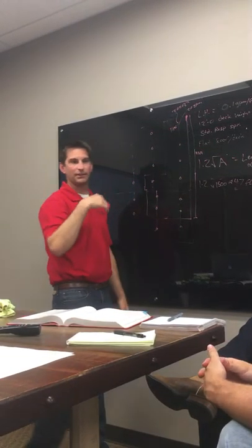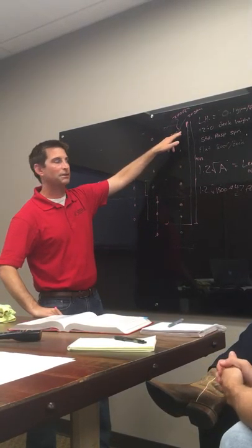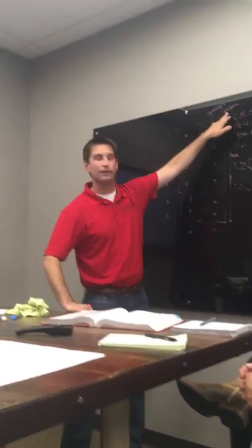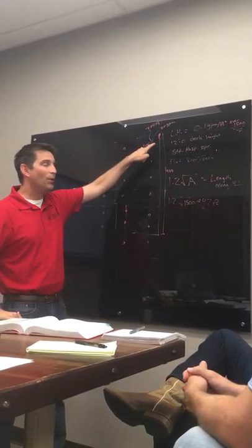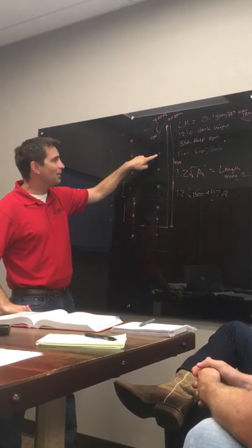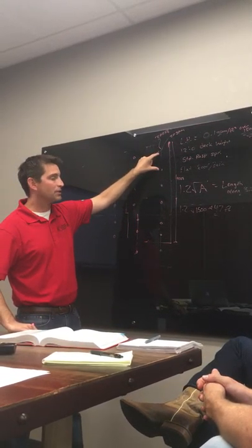Don't do any numbers, I don't think that'll work. Let's say you need 11 PSI for whatever K factor you have here to get 20 gallons a minute out of it. Now, in order to get 11 PSI to that end point, is the pressure going to be higher or lower at this point? It's going to be higher, because I have to overcome the friction loss for that pipe.